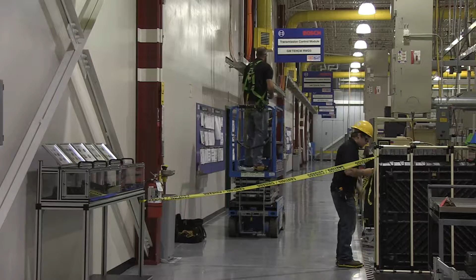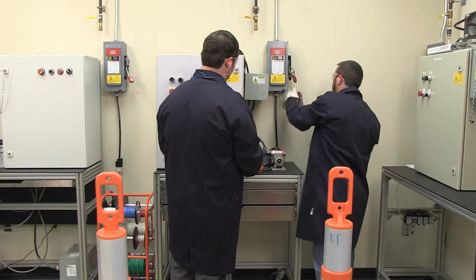As per OSHA regulations, control of hazardous energy, our lockout-tagout system maintains that each technician must be protected by his own lock and be trained and authorized by his local safety department. This applies to maintenance and repair. As for machine-specific procedures, all energy sources must be isolated and/or dissipated, and the procedures must be inspected annually. For specific information, always follow your site policies and procedures.